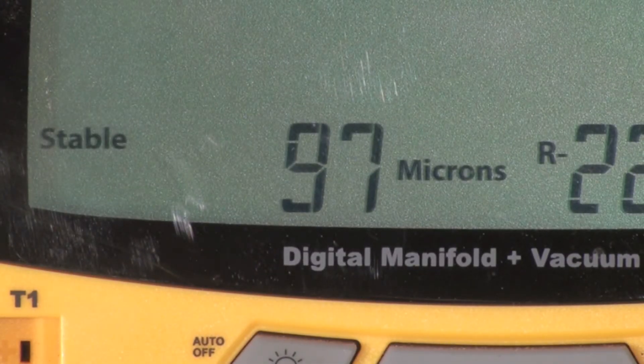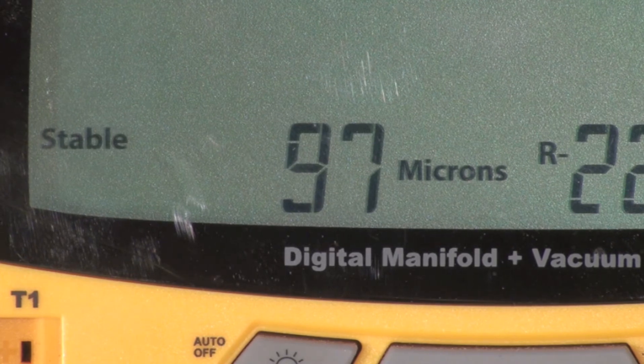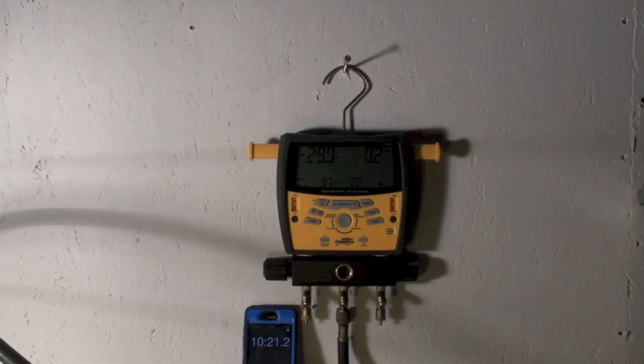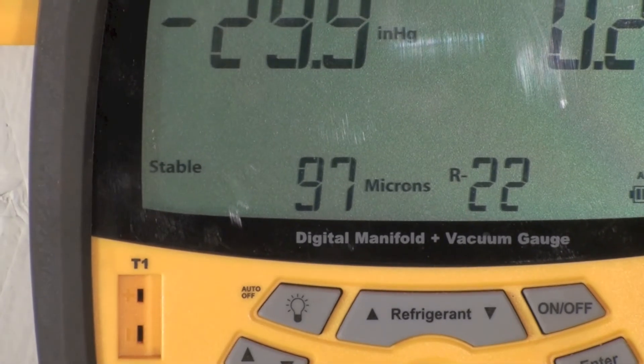Looks like we're pretty much settling out about 96 or 97 on the microns. About 10 minutes. So it looks like 97 microns is about what we're going to get in 10 minutes. And it's pretty stable.